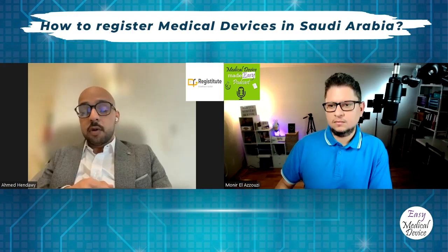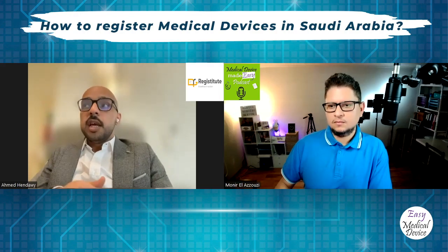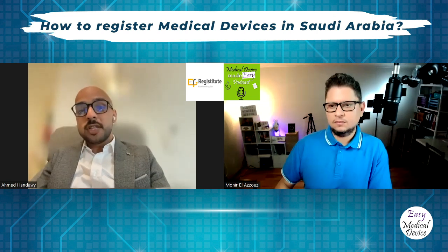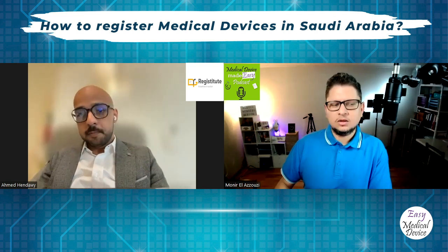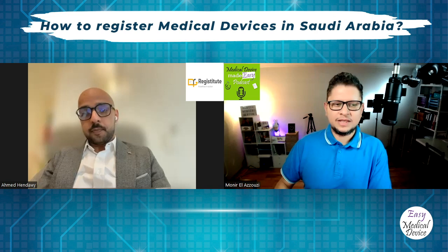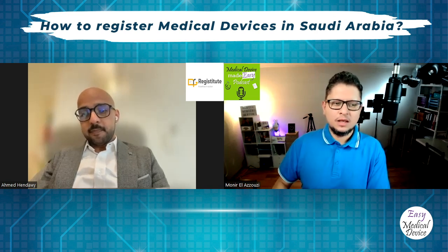Of course, everything is done through your authorized representative. So it's either an adverse event that has to be reported immediately, or other complaints that do not affect the patient or health in general, which can be compiled and sent to SFDA on a monthly basis, for example. Okay, so it's not really the same as Europe's requirements or EU MDR requirements.